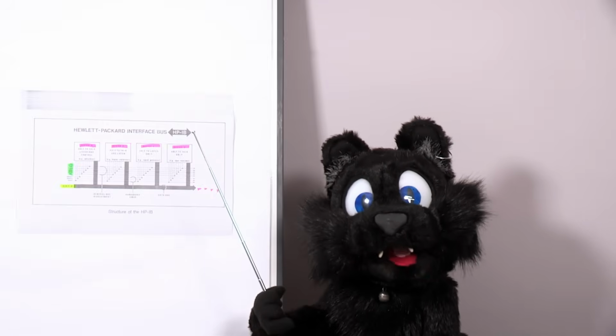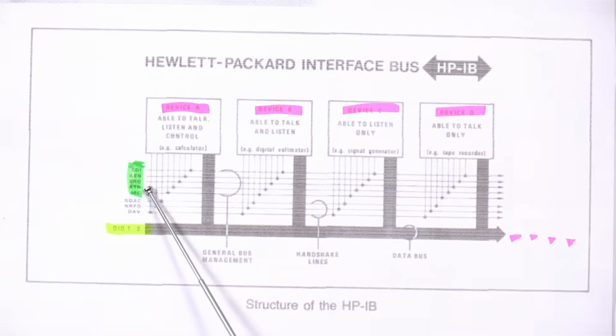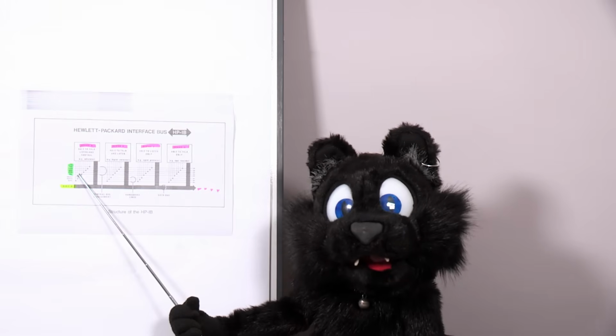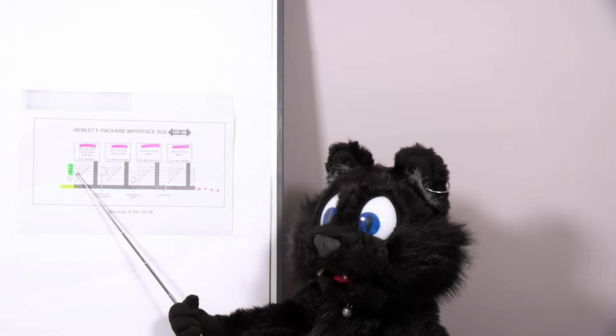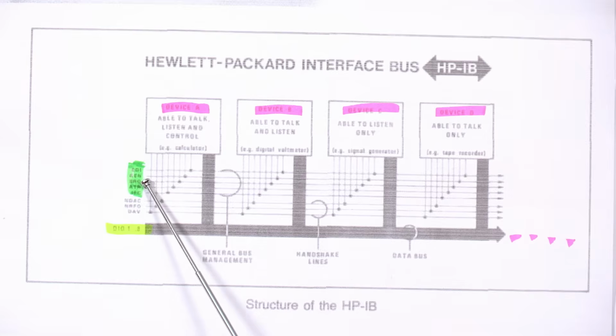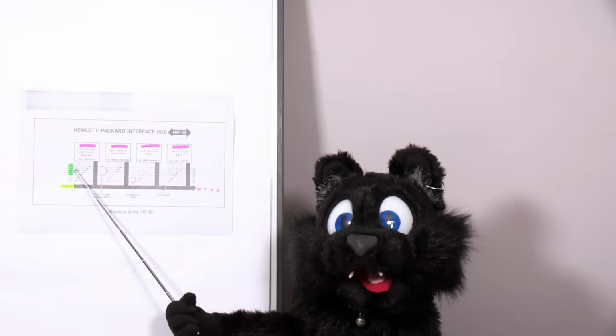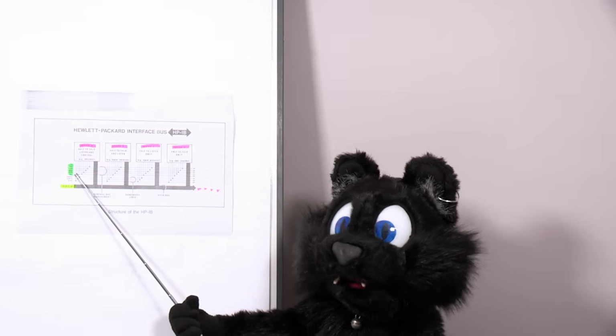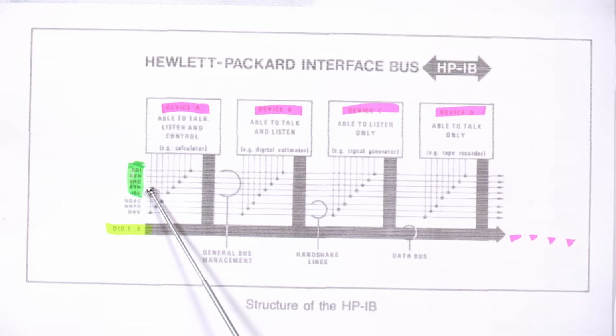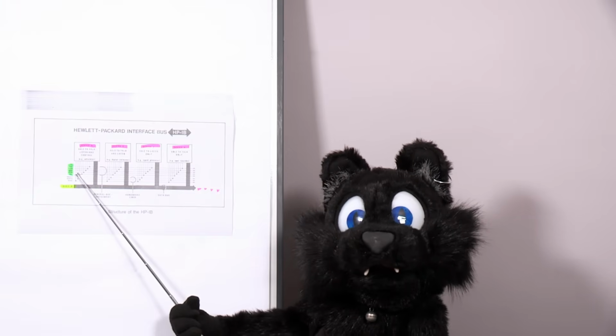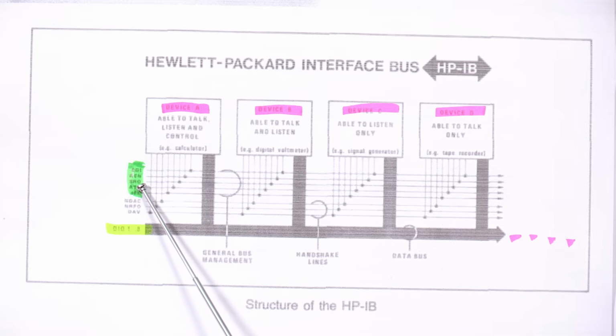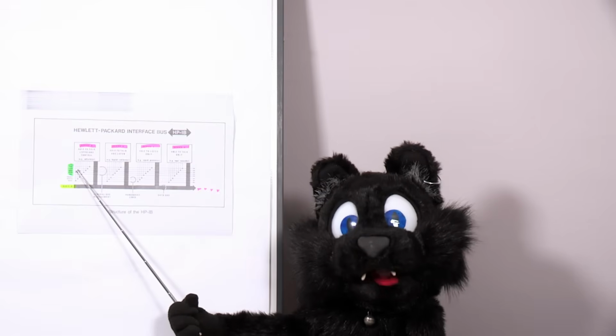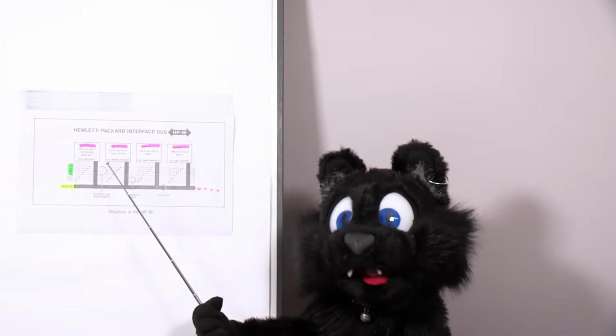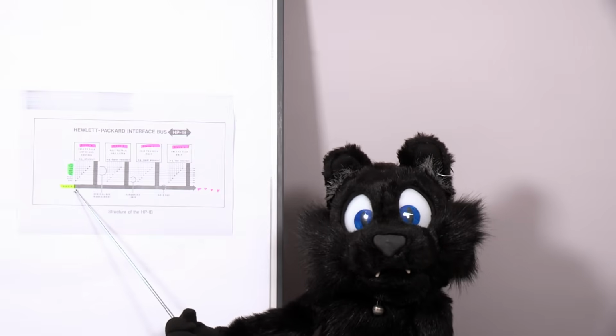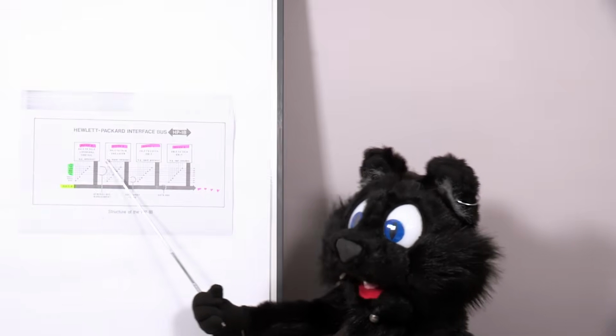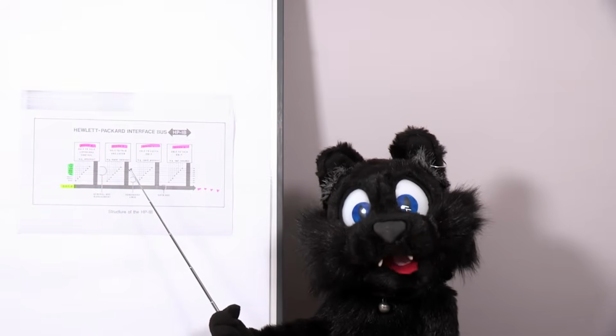Finally, there are a few control lines. IFC, interface clear, is used by the controller of the bus to force a full reset. REN, remote enable, tells the devices to go into the remote mode when they receive their data. ATN, attention, is used by the controller to indicate a command rather than data is on the bus. SRQ, service request, is asserted by any device to call for attention, kind of an interrupt request to the bus controller, which then needs to scan the bus, called serial polling, to find out who was knocking.